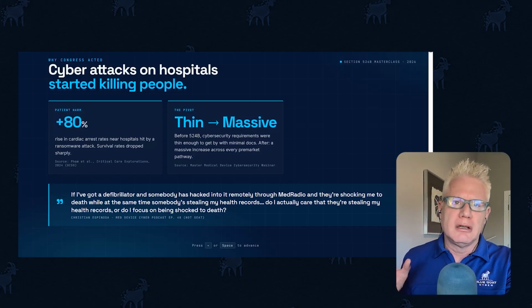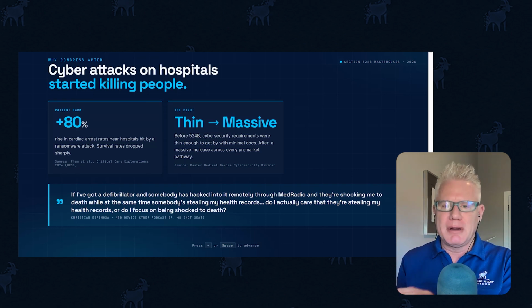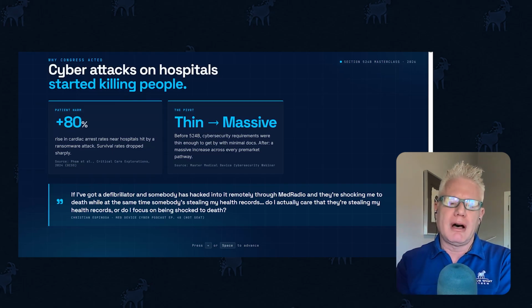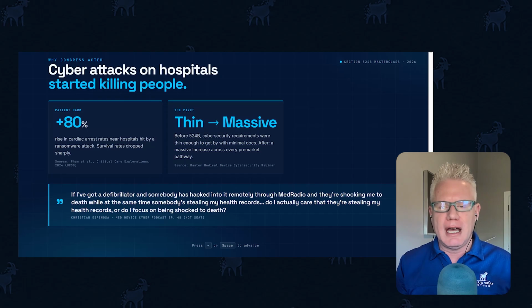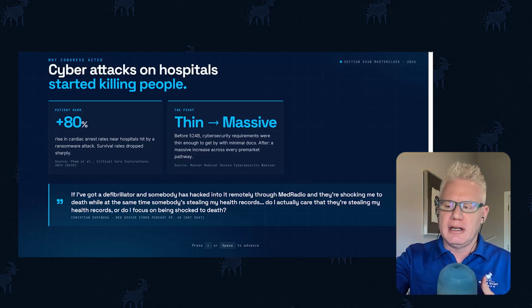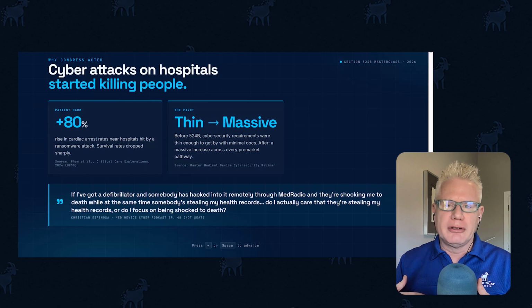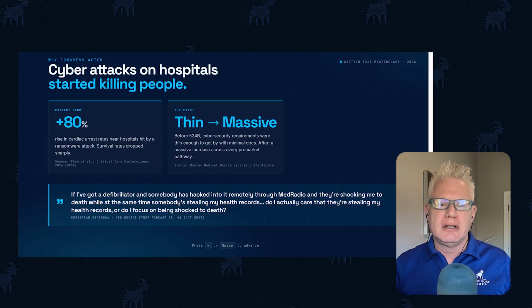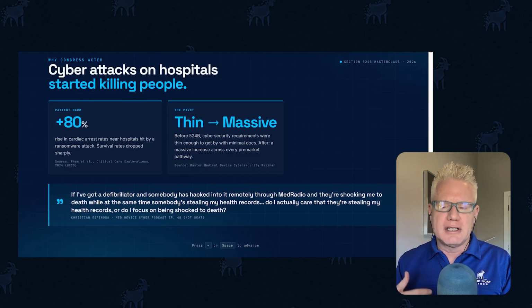And a lot of people still think medtech cybersecurity is about the data, and I have a lot of discussions with people about this. It is about the data, but the data is really secondary. There's a quote from me on the bottom here, and this just puts things in perspective. If you have an implantable like a defibrillator, and there have been compromised defibrillators, Dick Cheney had the wireless capability of his defibrillator removed. But if you have an implantable, such as a defibrillator, and somebody has compromised it wirelessly, and they're able to shock you at their will, while at the same time they're still in your protected health information, which one is a priority? You can recover from your protected health information or your sensitive data being stolen, but you can't recover from being shocked to death. And this is the world we're starting to live in.